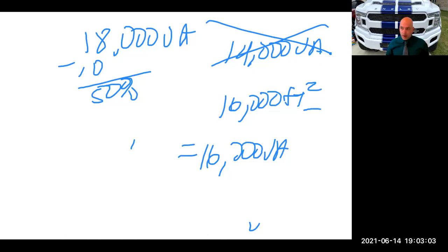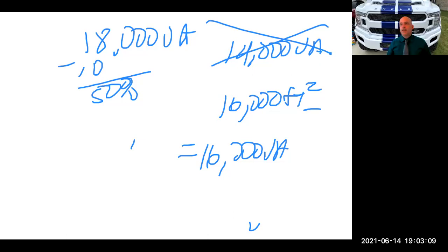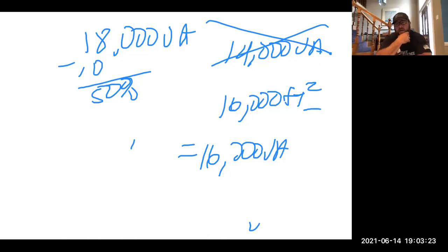Nipple fills are 24 inches or less. And the wire ampacity derating for the number of current carrying conductors doesn't start until after 24 inches. So there are some tie-ins there, but it's not the circular mils that you use; it's the area in square inches of the conductor, with the insulation. Right.